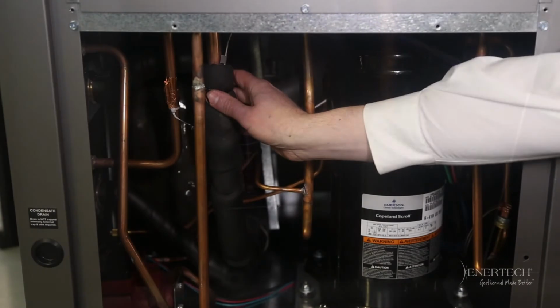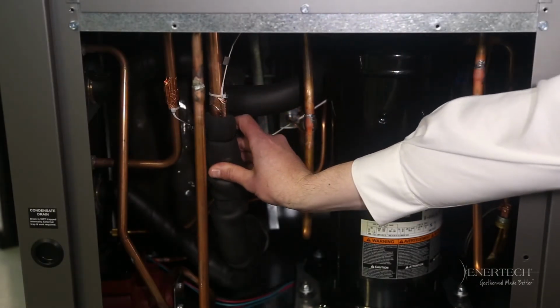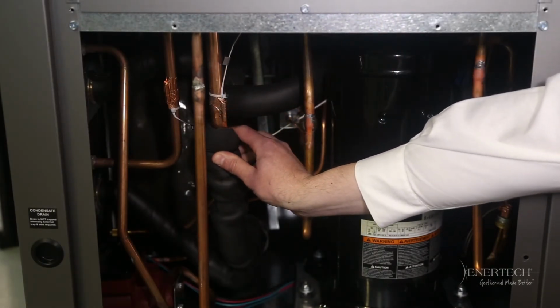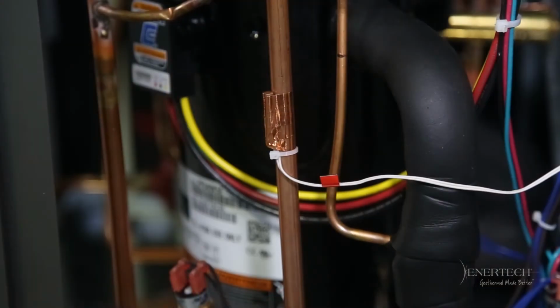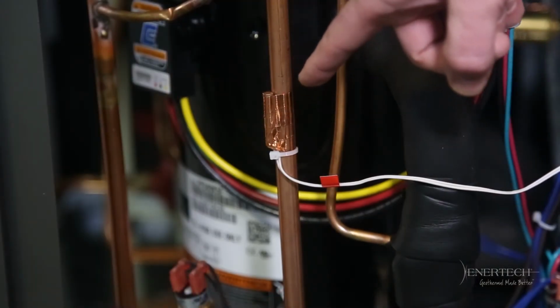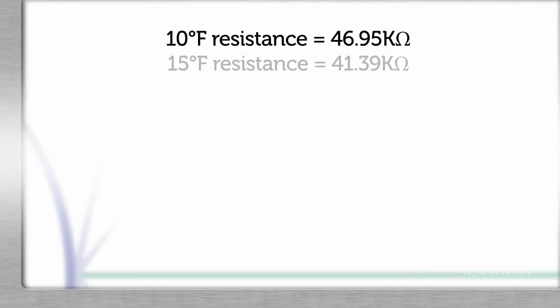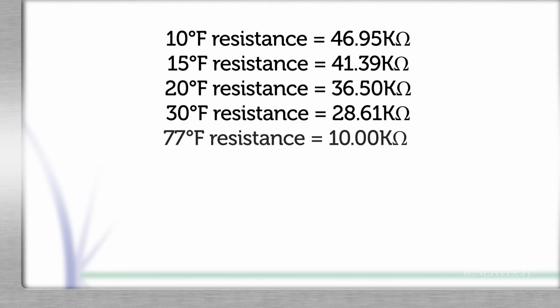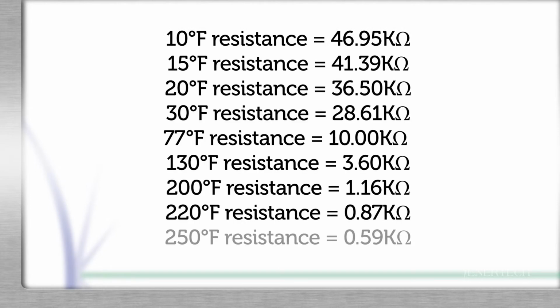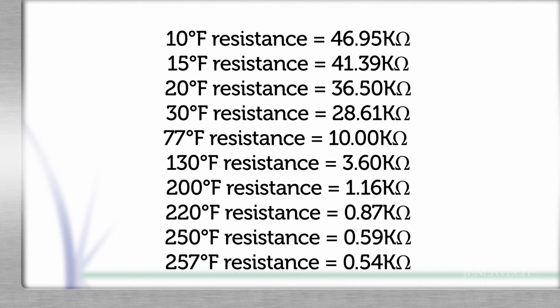Sensors are semiconductor sensors. If they go bad, it would be either open or shorted. As a general statement, sensors rarely fail. Make sure the sensor is in good contact with the tubing before you condemn it as bad. For example, at 30 degrees Fahrenheit, the sensor resistance would be 28.61 kiloohms, and at 77 degrees Fahrenheit, the resistance would be 10 kiloohms.